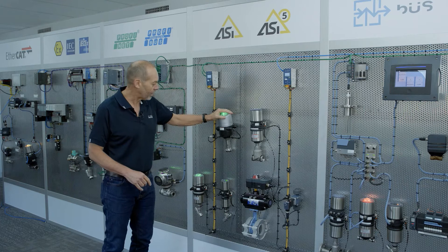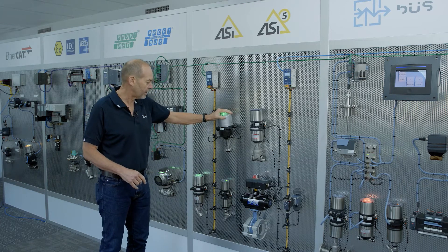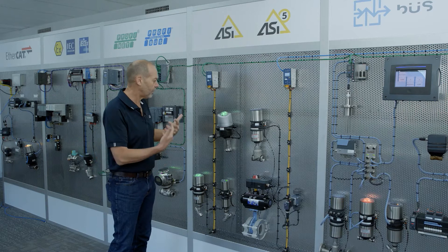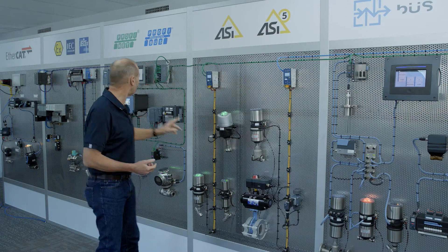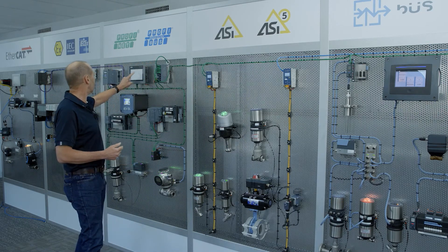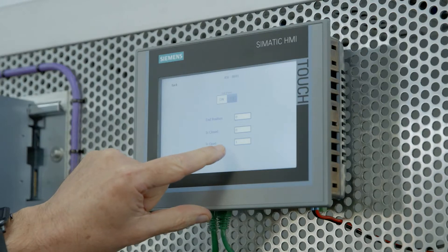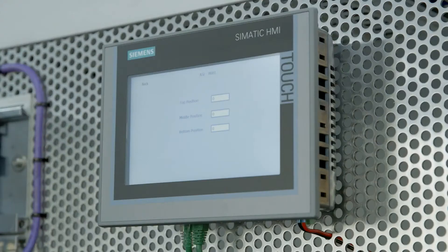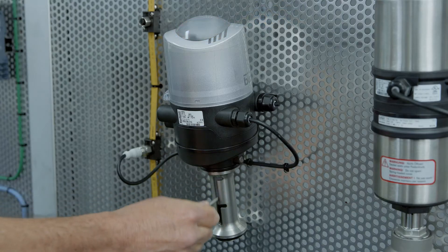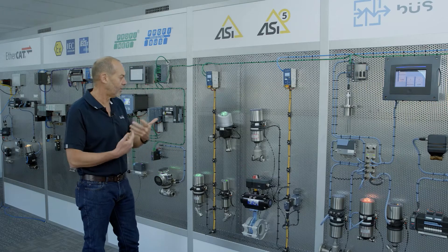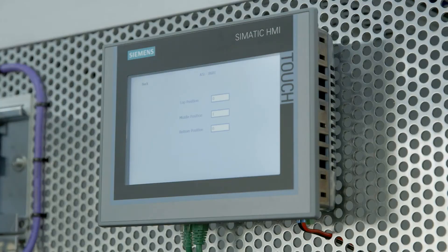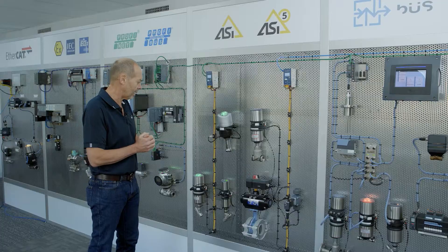To give you another example, we have one of our control tops here for multi-position valves, maybe in a mix-proof valve arrangement. We're seeing it in the bottom position — if I come back over to the screen you can see it's in the bottom position. As I move it to the open position you see it change over here, as well as to the mid position where the valve seat lifts for CIP cleaning, and you can see that also read back into the main system.